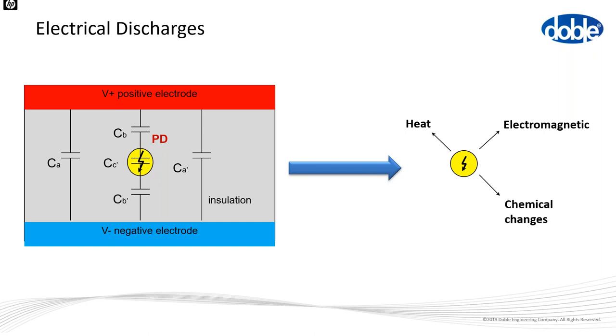The third effect is chemical change, and finally acoustics — a sound wave, the thunder accompanying every electrical discharge due to rapid expansion from localised superheating. This vibration is in the audible range but can go up to ultrasonic. Acoustic sensors are commonly used for passive equipment such as switchgear, transformers, and cables, but we tend not to use them for rotating plant because there are high ambient acoustic noise levels.